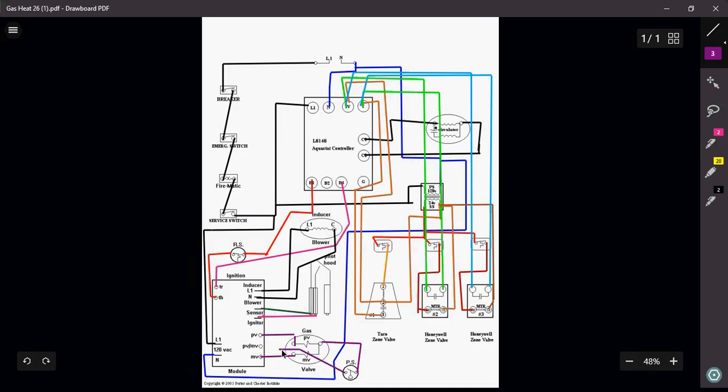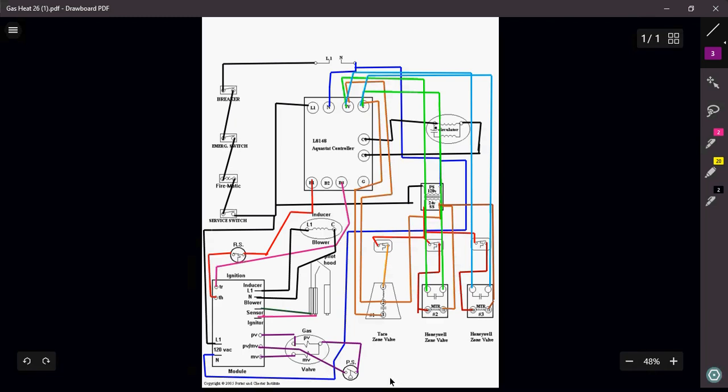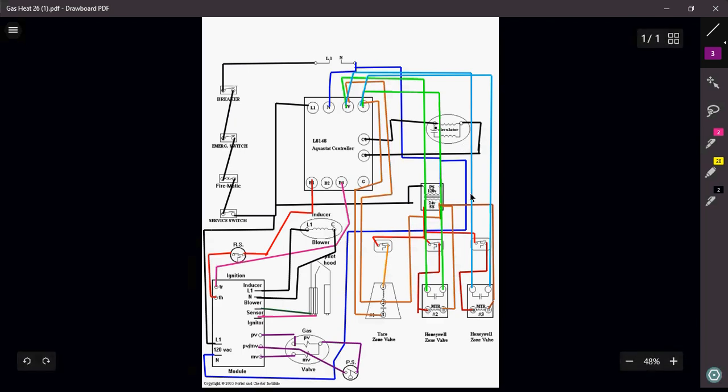So I'm just going to simply wire my pressure switch in with the common of my gas valve. So as my gas valve, if there's anything to be wrong with my vent motor, my flue pipe being clogged, my combustion chamber being clogged, broken or what have you, that pressure switch would not be able to close. And if that pressure switch is not able to close, I cannot energize my gas valve. My gas valve will not deliver my gas to my burners and I will not ignite.